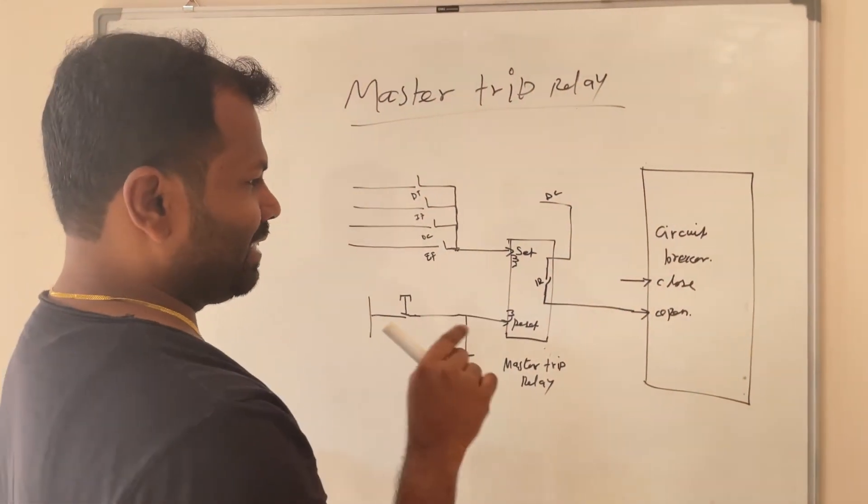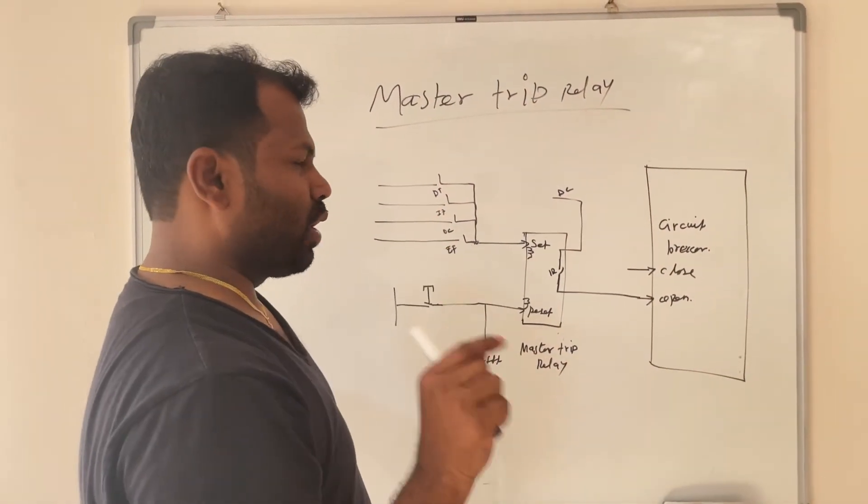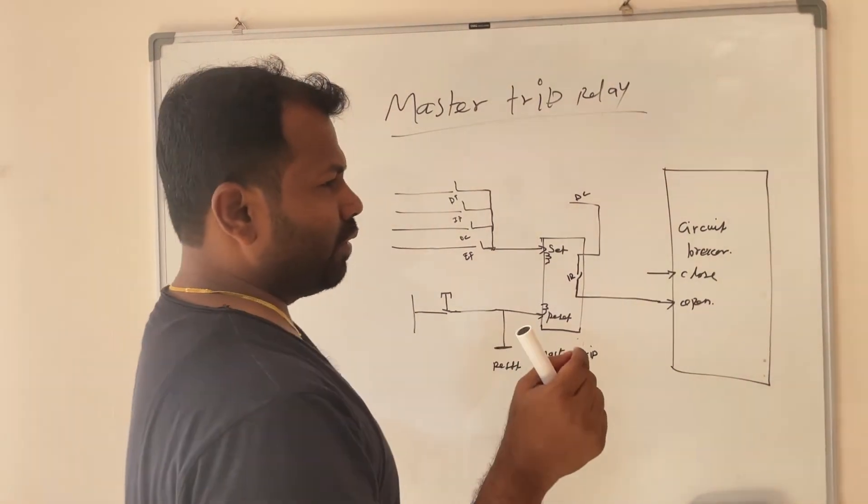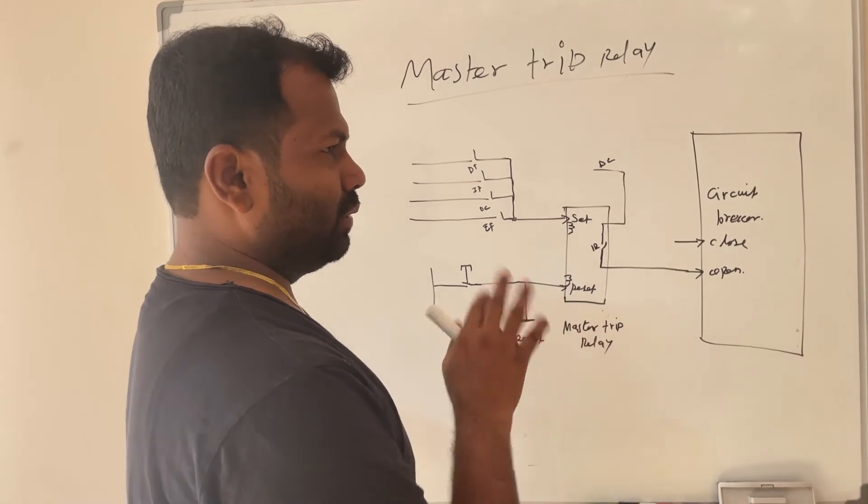This master trip relay will have multiple NO contacts. One NO contact will be used to trip the breaker, other NO contacts will be used to take feedback of this master trip relay.